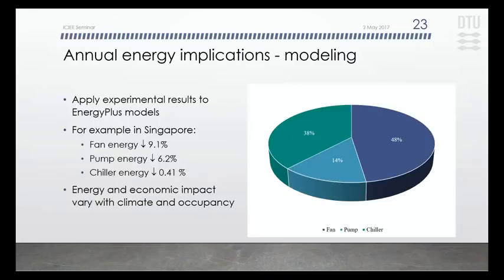So if we take those results and embed them in an energy simulation of a whole building for a year, what we found was for an office building in Singapore, about a 9% reduction in fan energy, 6% reduction in pump energy, and a 0.4% reduction in chiller energy. But interestingly, because the compressor on the chiller consumes a lot of power, 48% of the energy savings were from that 0.4% impact on the chiller, at least in the simulation.